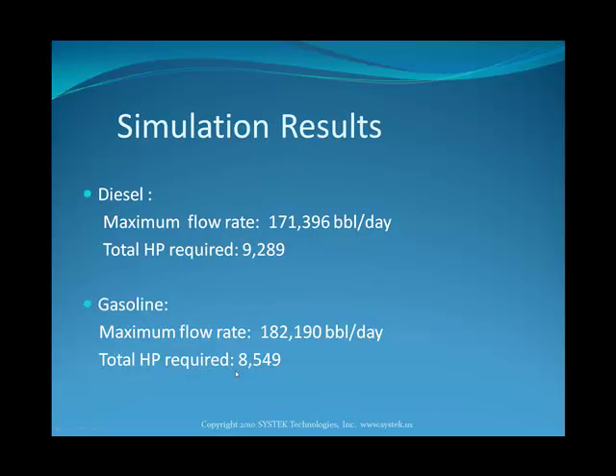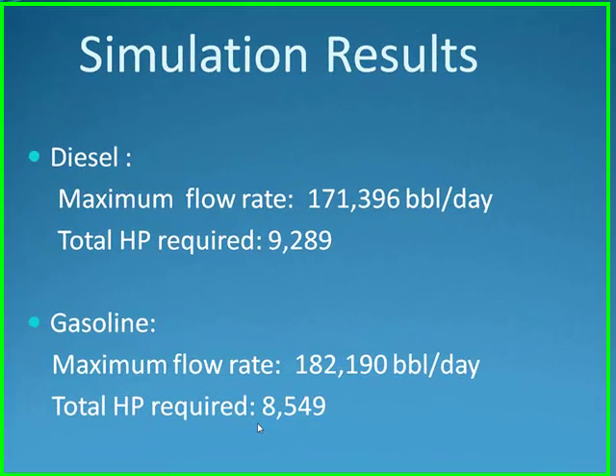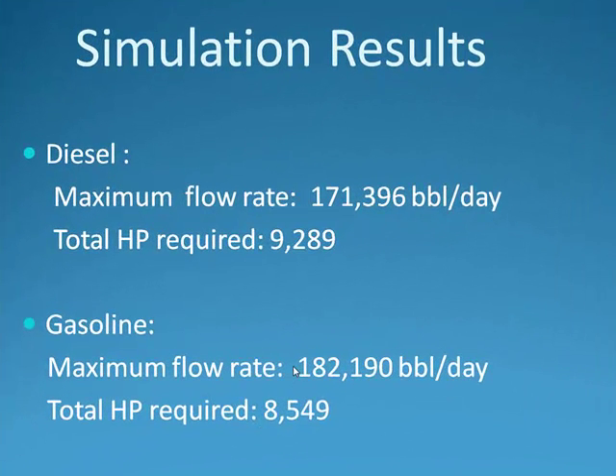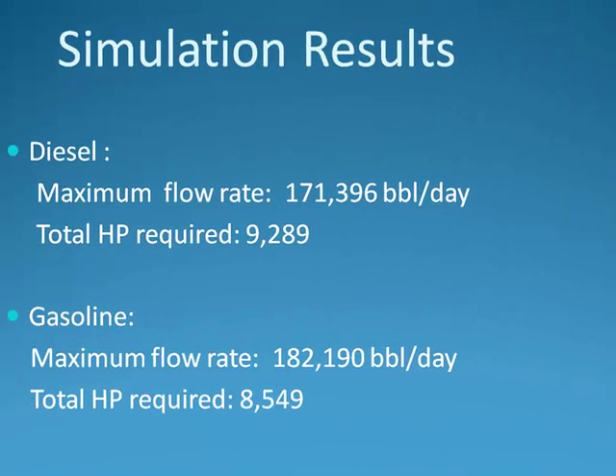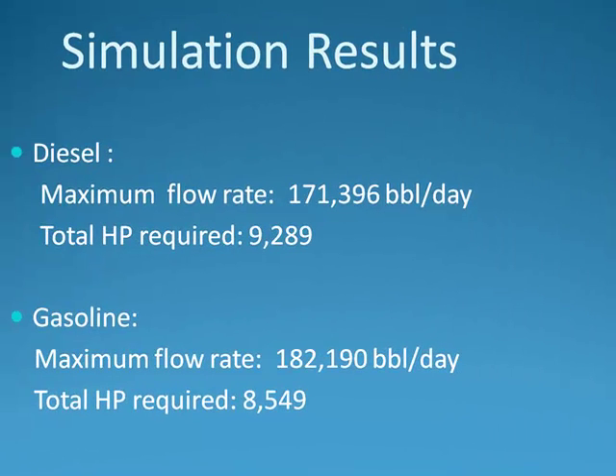Okay, the results of the simulation are as follows. For diesel, we have a maximum flow rate of 171,396 barrels per day with a total HP required of 9,289. And for gasoline, the maximum flow rate is 182,190 barrels per day with a total HP required of 8,549.